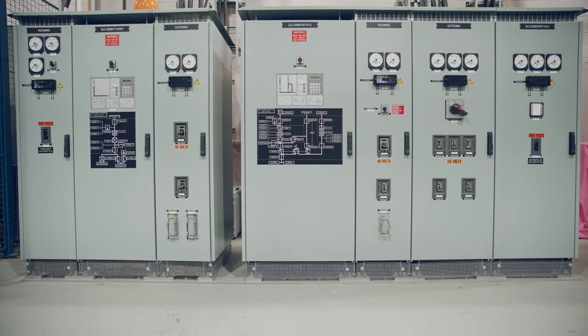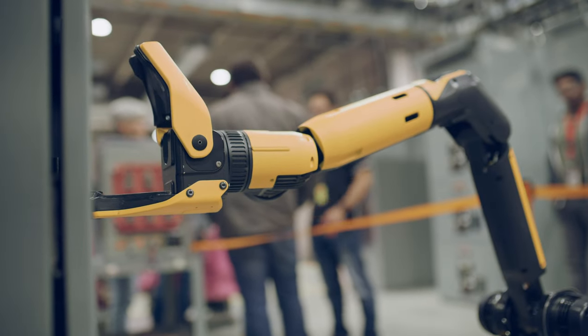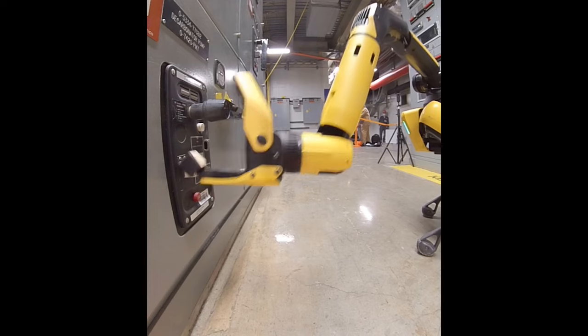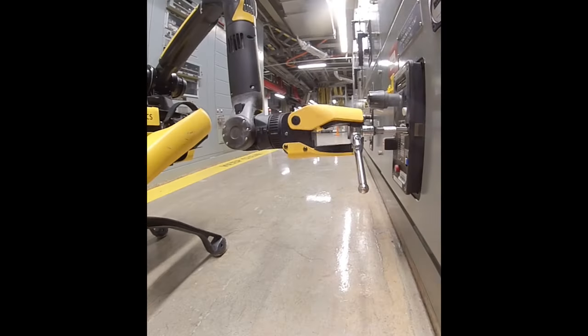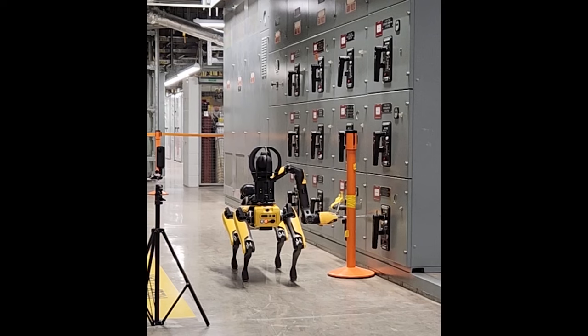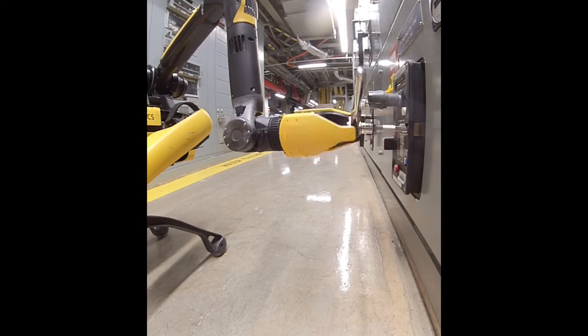What we were able to do with some real practice in the Darlington Learning Centre breaker lab — where we had a similar model of that breaker — was to practice both the tripping of the breaker with the arm and then the ratcheting out using a socket. We were also able to get some support from Boston Dynamics directly for the ratcheting motion, so that when we were trying to rotate the tool, the arm had a special built-in function that was able to do that quickly for us. With a lot of practice and some effort in the lab, we got the confidence to say we can go execute this in the field.